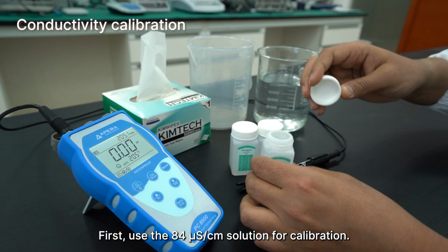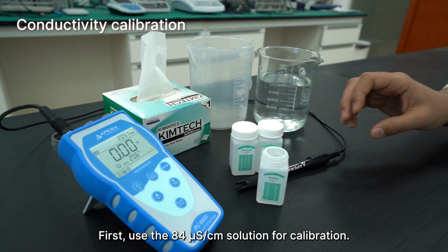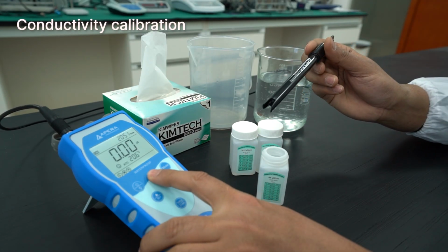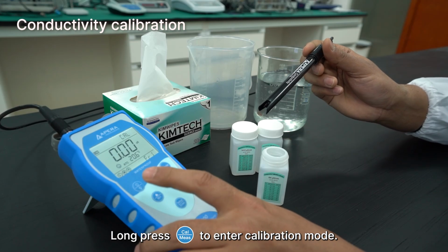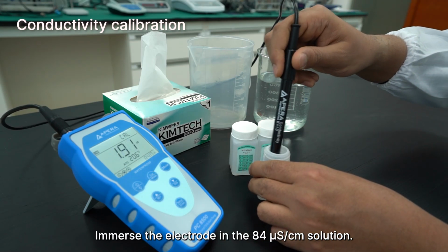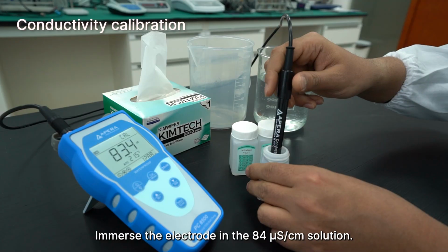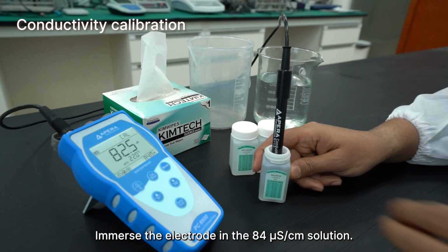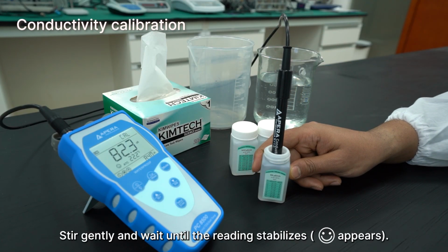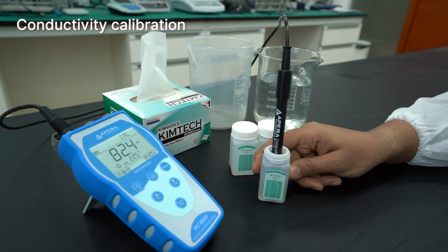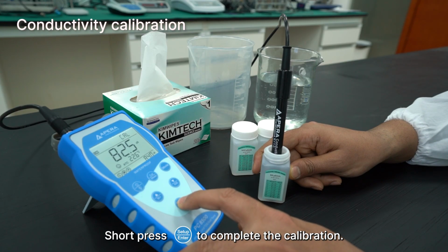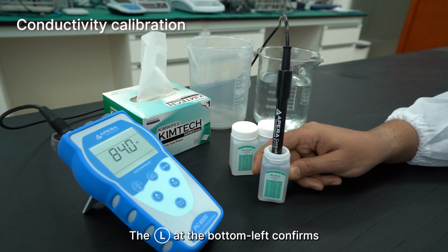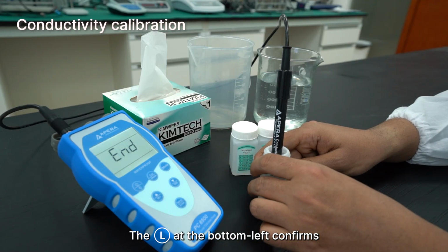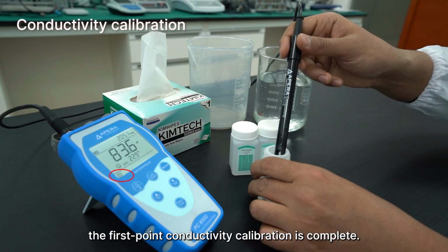First, use the 84 microsiemens per centimeter solution for calibration. Long press the cal button to enter calibration mode. Immerse the electrode in the 84 microsiemens per centimeter solution. Stir gently and wait until the reading stabilizes. Short press enter to complete the calibration. The L icon at the bottom left confirms the first point conductivity calibration is complete.